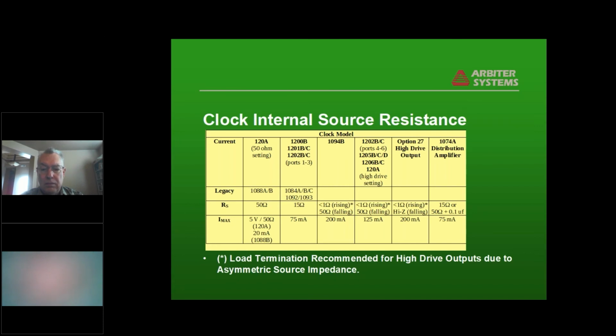And the four on the next three are all what we call high drive outputs. Those have the ability to generate over 100 milliamps of current to drive multiple loads. But because of the very low impedance on the rising edge, we recommend some sort of termination at the farthest load in order to keep the ringing from causing a problem.